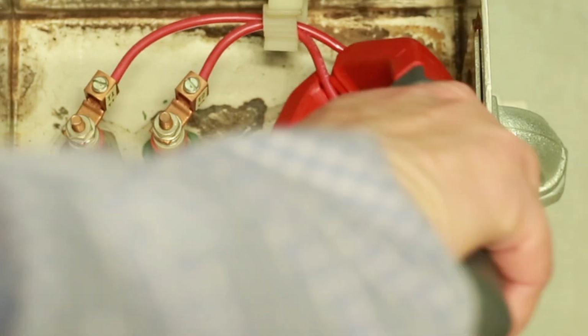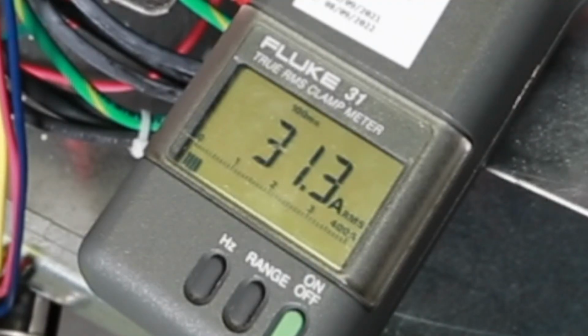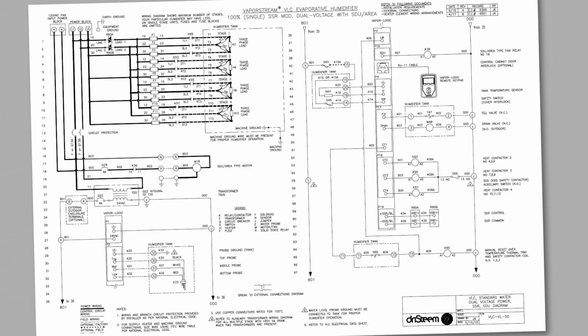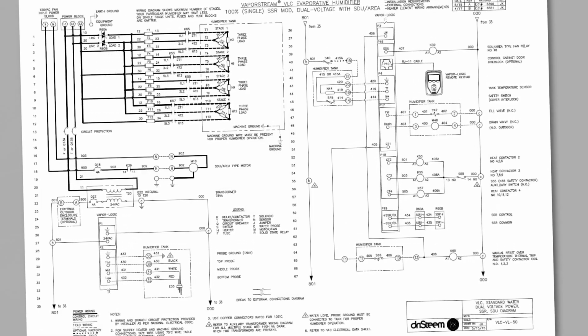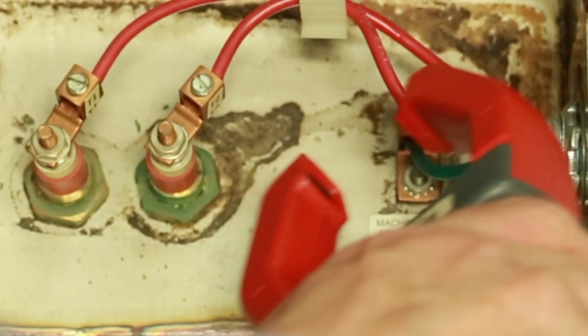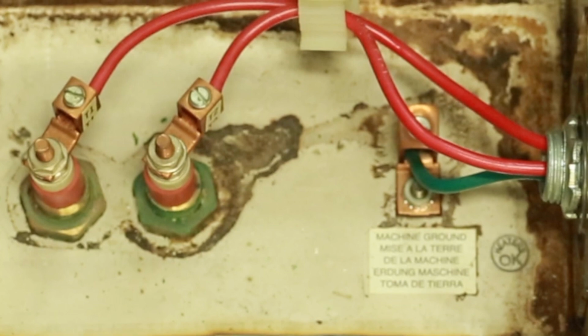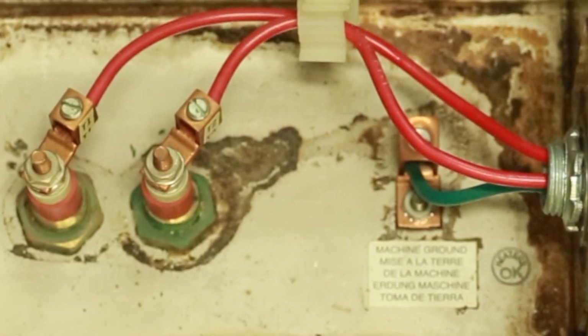And measure current draw of heaters and verify amp values per stage by comparing to the wiring diagram located inside the control cabinet. This identifies any burned out heaters. Only qualified electrical personnel should perform this task.